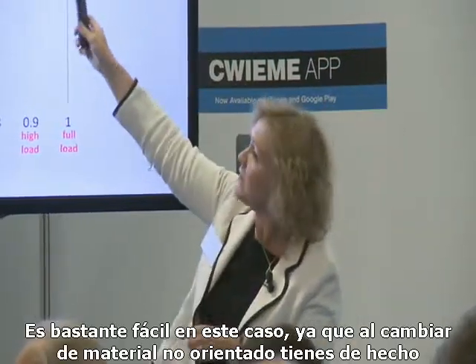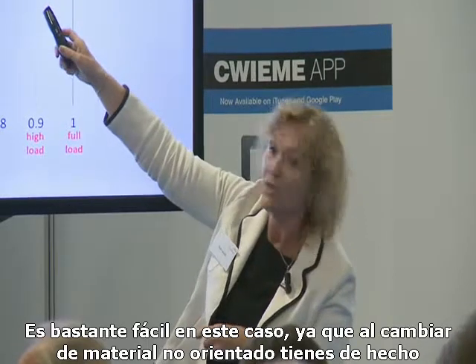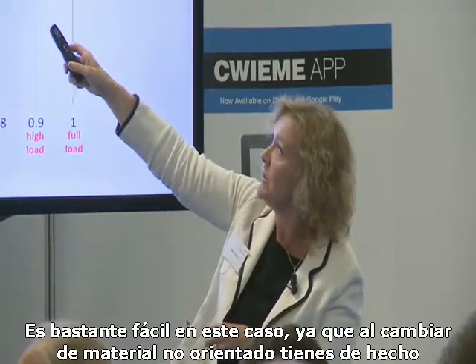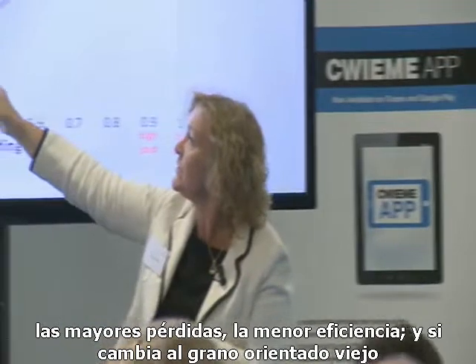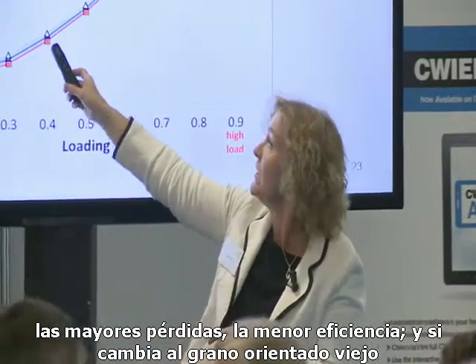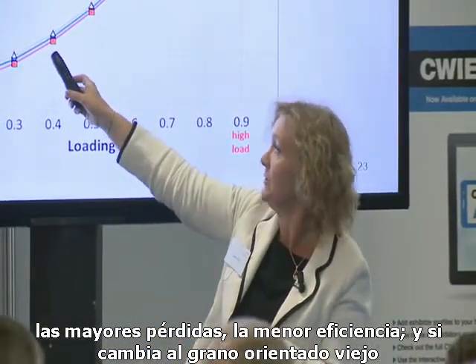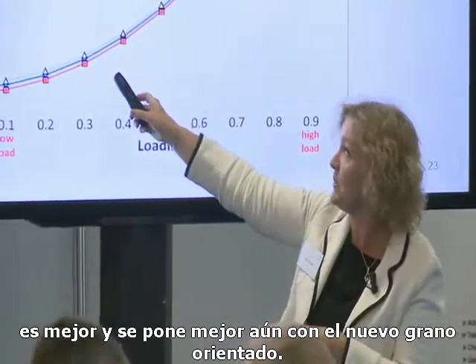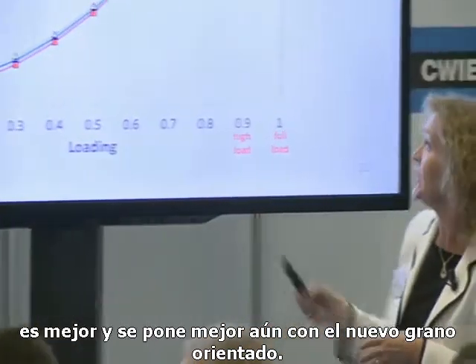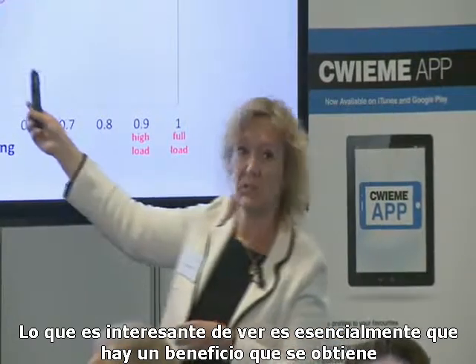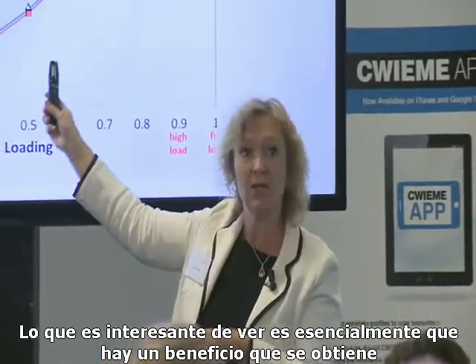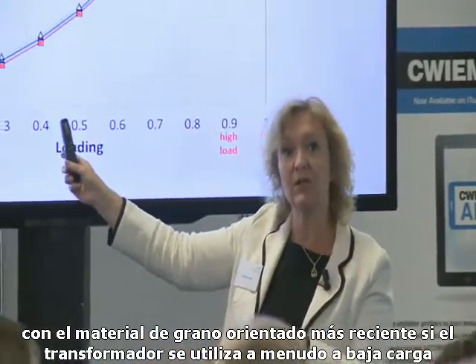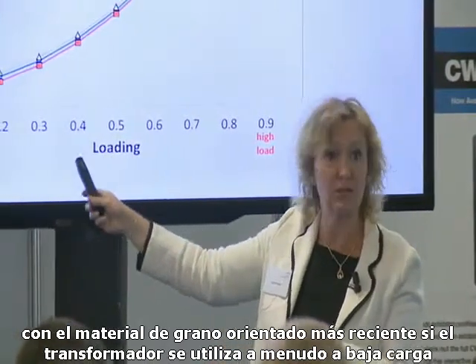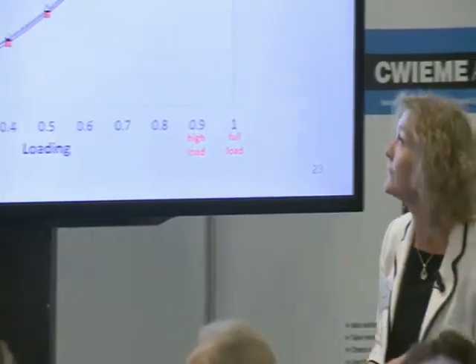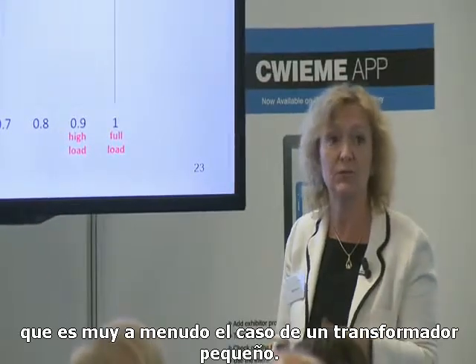It's quite easy in this case: when you switch from the non-oriented material, you have the highest losses, so the least efficiency. If you switch to the older grain-oriented, it gets better, and it gets better still with the new grain-oriented. What's interesting is that the newer grain-oriented material gives an essential benefit if the transformer is often used at low loading, which is quite often the case for such a small industry transformer.